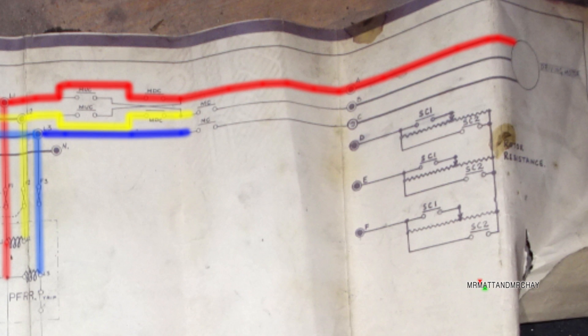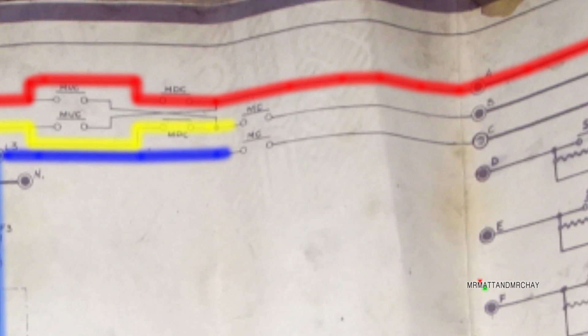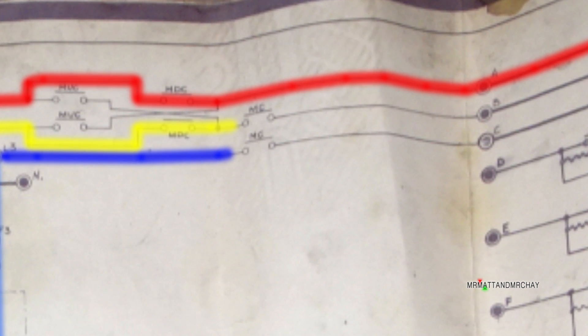The three coils on the motor must first form a circuit before the motor will do anything. As a failsafe, the main contactor breaks phase 2 and 3, preventing a circuit being formed. This is required because if any of the contactors were to get stuck, the lift would still stop when the main contactor turns off.